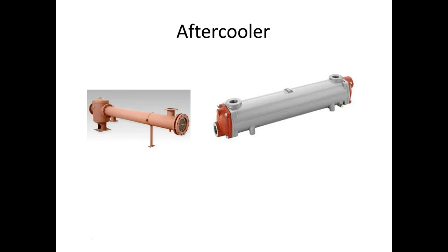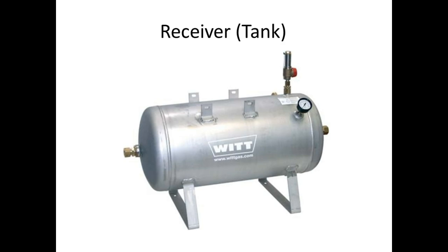Aftercoolers can be long tubes. A lot of times, some people call them chillers, where they actually run cool water on the outside of the jacket and then run the compressed air in the center. Receiver tanks, are you okay here? Not very much to them. Pneumatic tanks are going to have a drain at the lowest point, because it's almost impossible to keep water out of those tanks.